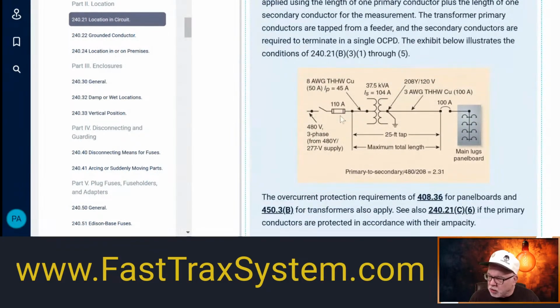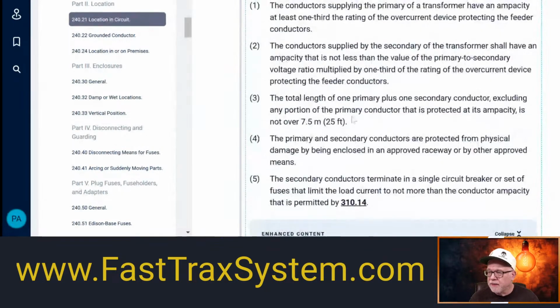Okay, so it looks like the overcurrent protection for the feeder is 110. So I'm going to do 110 divided by 3. And that gives me 36.66, okay? So that's the third. So what does the rule say? It says the conductor supplied by the secondary of the transformer shall have an ampacity not less than the value of the primary to secondary voltage ratio multiplied by 1/3 of the primary. So that was 36.66. So I'm going to do 2.31, multiply that by 36.66, and that is 84.68 amps.